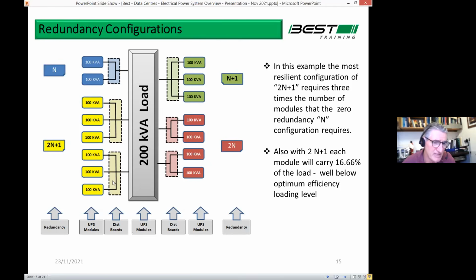And a step above that, that's used in some of the data centers, is 2N+1. So they have an A system and a B system, and in both systems, they have a spare module as well. So you can see, starting off with a basic need where just 2 100 kVA modules would meet your 200 kVA demand, you end up putting 6 in. So there's a massive amount of additional plant to put in data centers to meet this resilience element of the design.